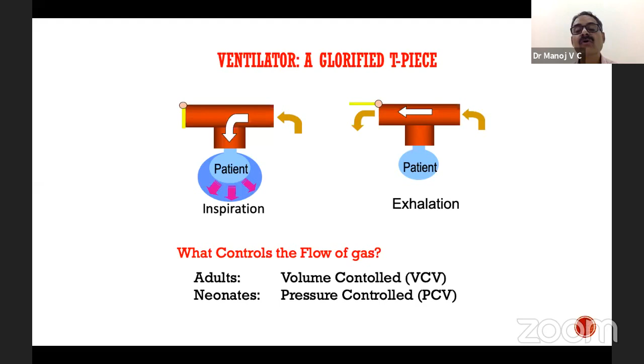So now, in adults, it's volume control ventilation. In neonates, by default it's always pressure control ventilation, which means that the flow of gas is determined by some pressures that you limit. Now, let me explain this concept a little more. You have a continuous flow of gas which will generate pressure, because we said ours is pressure control ventilation, PCV. Once you generate this pressure, the pressure is let go, and it will go from high pressure to low pressure.